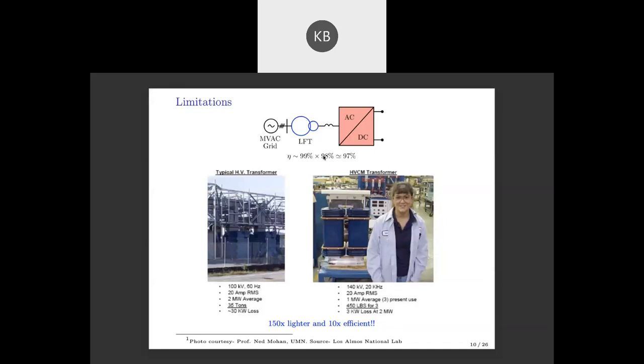The peak efficiency that you can easily achieve with a proper design on this inverter is in the ballpark of 98% with silicon IGBTs. And if you use silicon carbide, which is of course more expensive, you can switch it maybe close to 50 kilohertz and still achieve an efficiency close to 99%. Silicon IGBT is close to 98%.